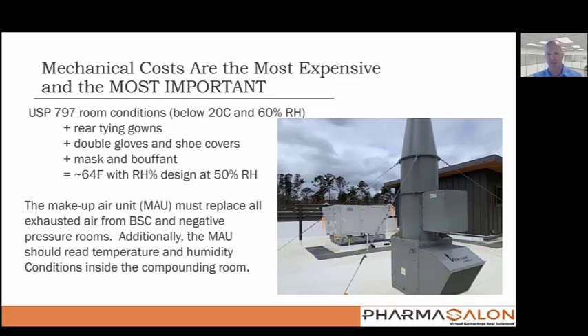You cannot dump air out of a building for non-sterile 12 times an hour, 24 hours a day, over and over and over, constantly dumping air out of a building and not expect to have to replace it. Same on the sterile side. ISO 7 buffers are doing a minimum of 30 air changes per hour, and all of those 30 air changes are going out of the building 24 hours a day because you never shut down a clean room. You never lose control over that controlled critical space. And I can tell you, and mark my word, this is not up for debate: if you put air out of the building, you've got to replace it. That is not negotiable, and that takes a dedicated makeup air unit in some form or fashion.